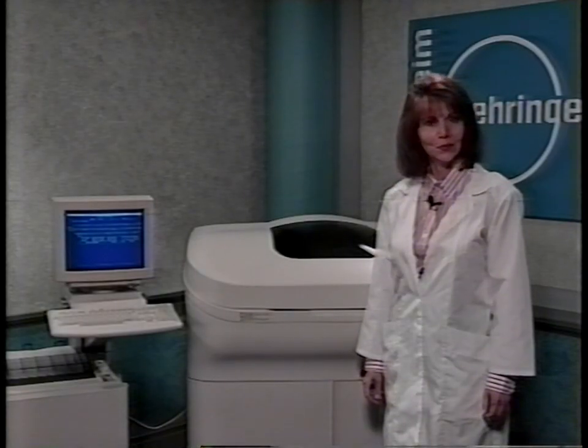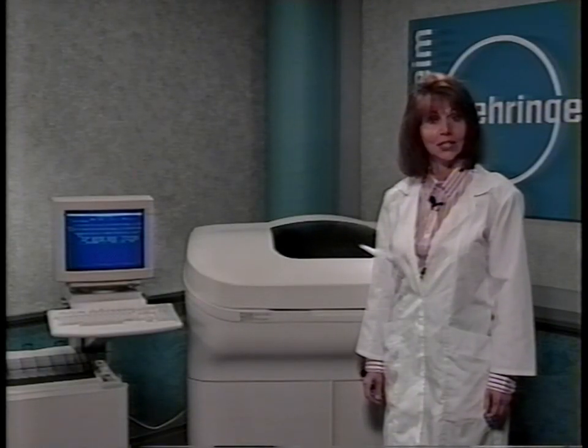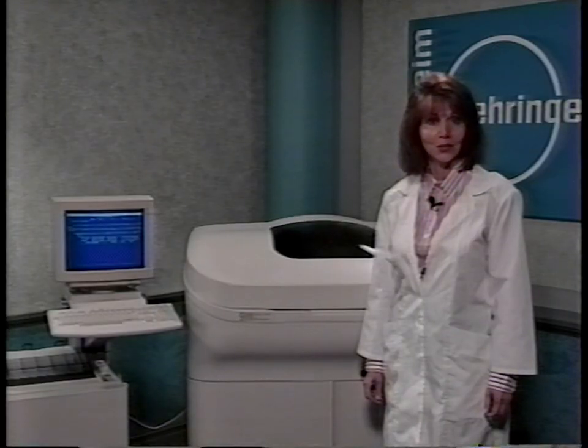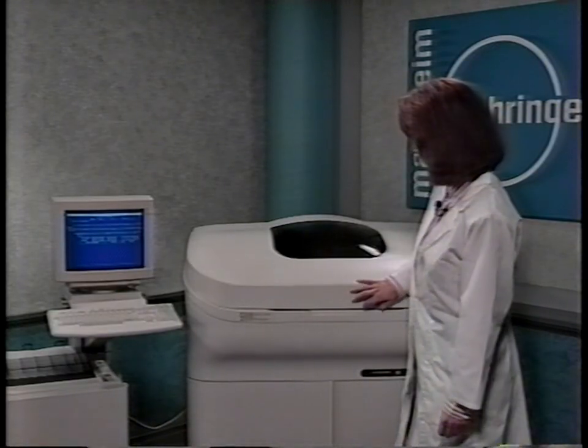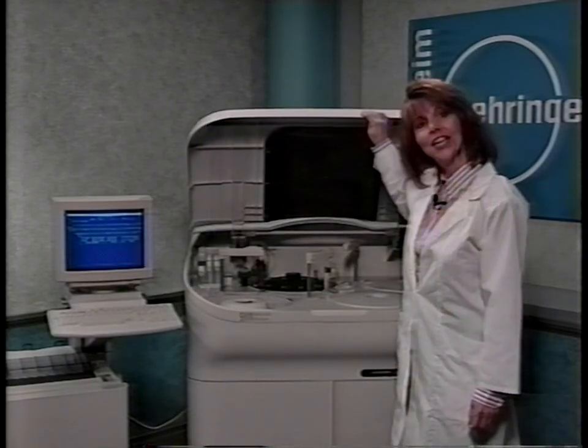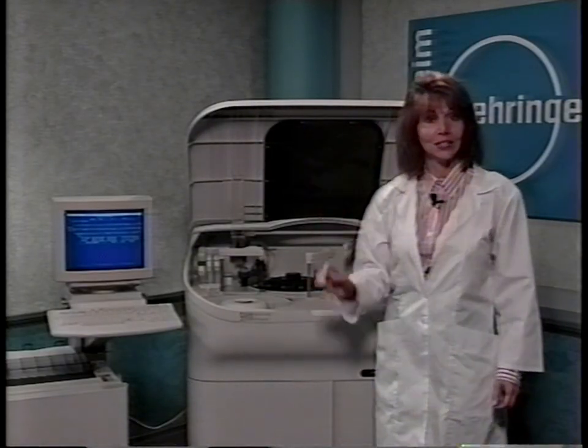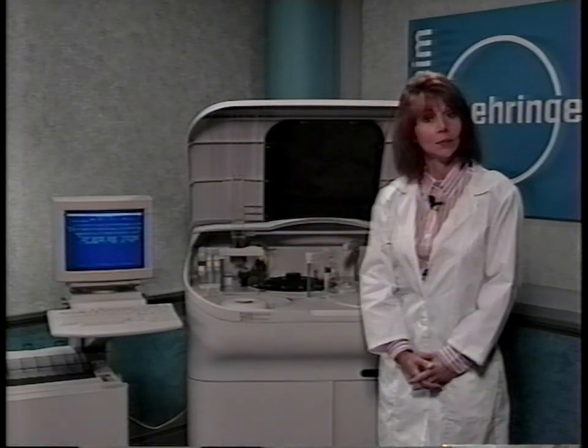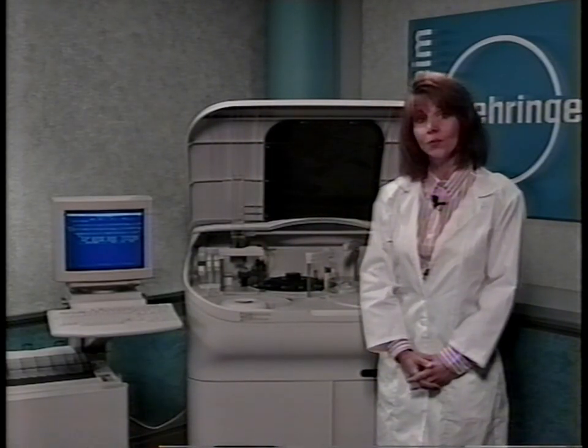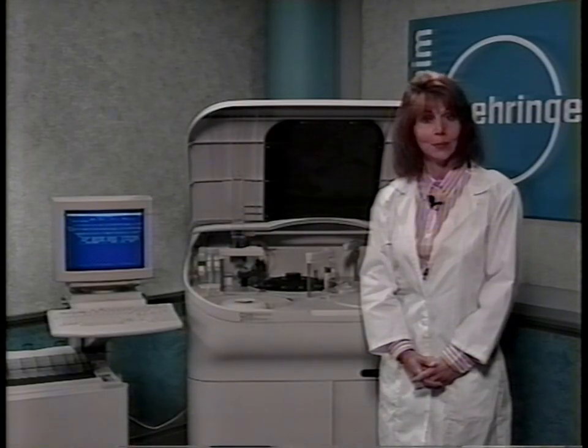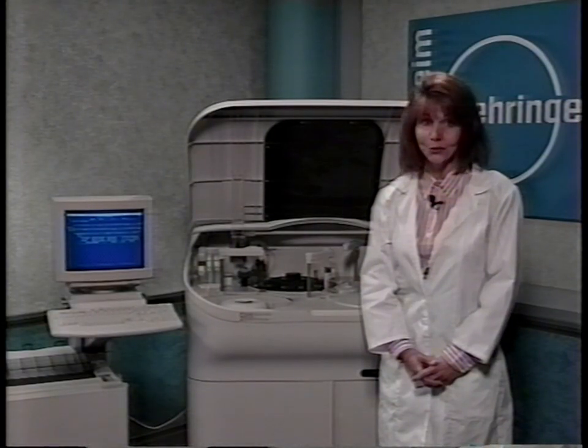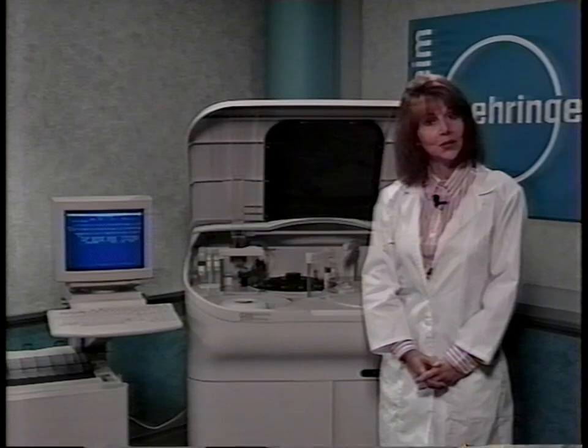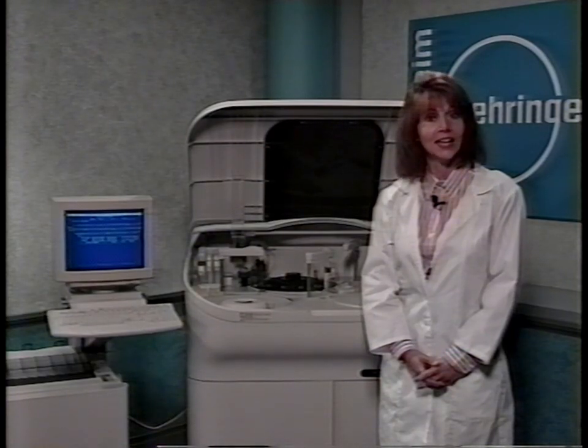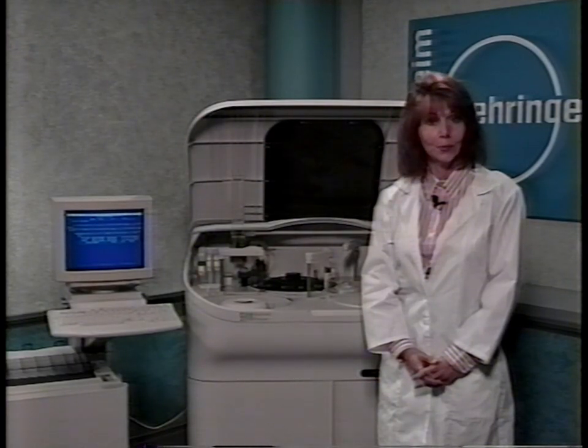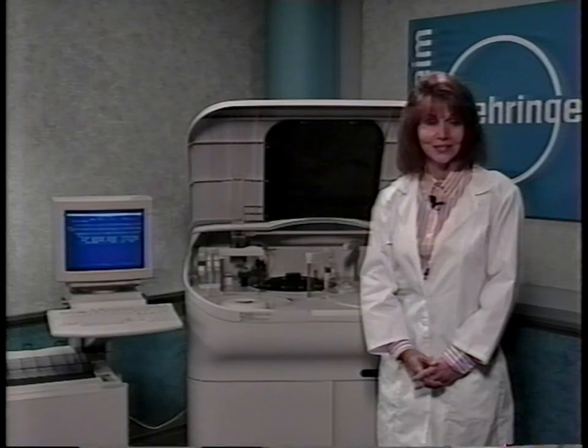The tests are performed by the analytical unit using its photometric and potentiometric measuring systems. The potentiometric or ISE system performs the sodium, potassium, and chloride tests by voltage measurements of ions in diluted samples using ion selective electrode cartridges. The photometric system performs all the other tests by measuring the light transmitting properties of their chemical reactions.